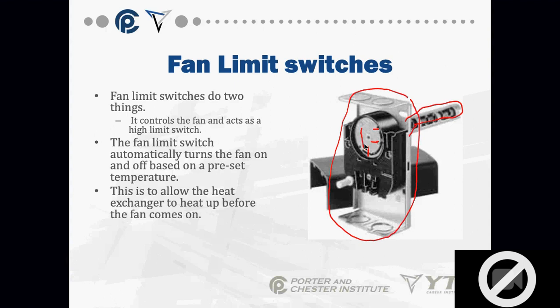Again, on oil forced air equipment, you see a ton of these. On gas equipment, you're starting to see less and less of these. They're starting to go away. So what the fan limit switch does is two things. It controls the fan, which is the blower that blows air around a room, and it also acts as a high limit switch. The fan limit switch turns on the fan at a preset temperature, and it turns off the fan at a preset temperature. The whole purpose is, A, we don't want to blow cold air around the house, and B, we want to make sure the furnace cools off when it's done. All of that is handled by this limit switch on the fan side.